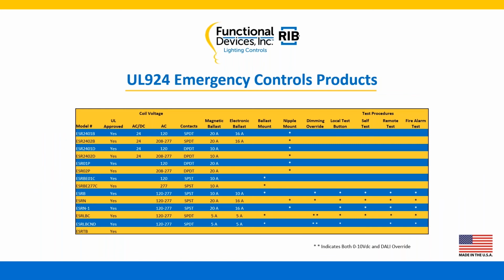Here we give you just a table of our UL 924 emergency control products. Simple table. We pretty much share this with our literature that we send out. If you were looking for an electronic ballast rating of 10 amp, you go to the electronic ballast column, you pull out the 10 amp, and you see that's an ESRB model. Now you look across and you can say, oh, it's a ballast mount, and it definitely is not a nipple mount. It has dimming override. It has the local test button. It has a self-test. It has a remote test. It has a fire alarm input. So what we're really trying to do with this is give you easy access to what our models do and what they support.